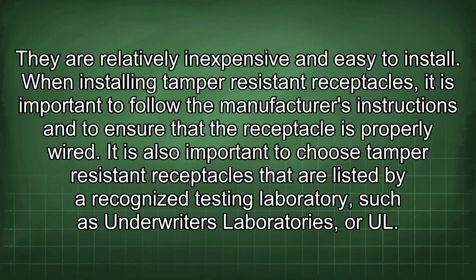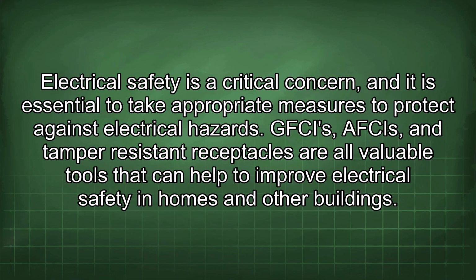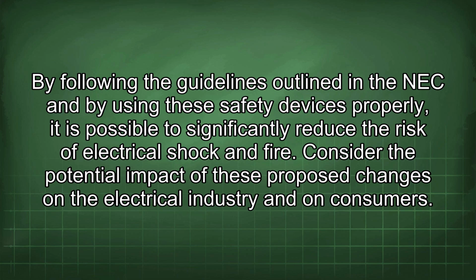When installing tamper-resistant receptacles, it is important to follow the manufacturer's instructions and to ensure that the receptacle is properly wired. It is also important to choose tamper-resistant receptacles that are listed by a recognized testing laboratory, such as Underwriters Laboratories, or UL. Electrical safety is a critical concern, and it is essential to take appropriate measures to protect against electrical hazards. GFCIs, AFCIs, and tamper-resistant receptacles are all valuable tools that can help to improve electrical safety in homes and other buildings. By following the guidelines outlined in the NEC and by using these safety devices properly, it is possible to significantly reduce the risk of electrical shock and fire.